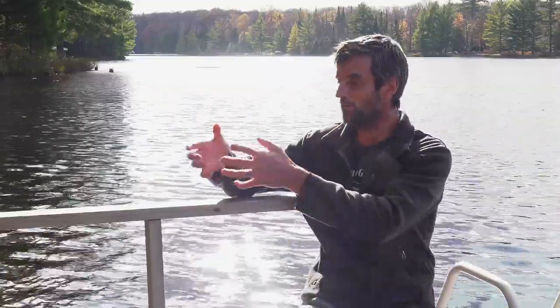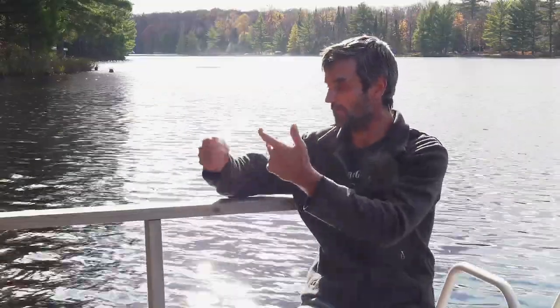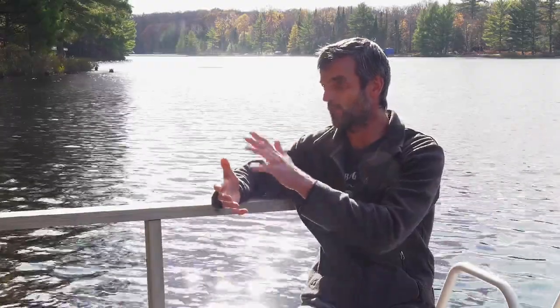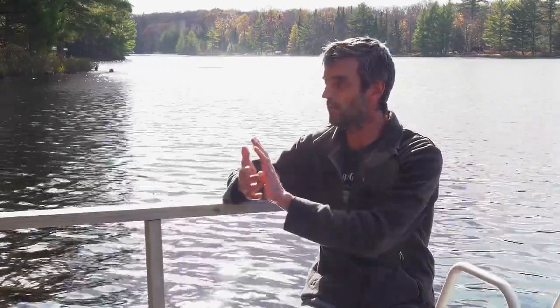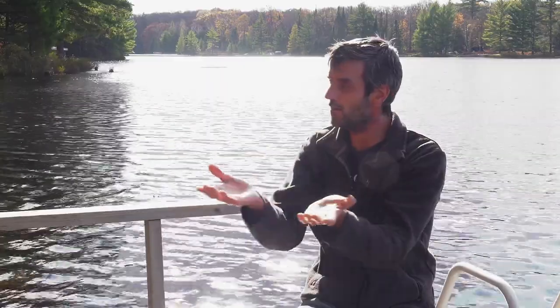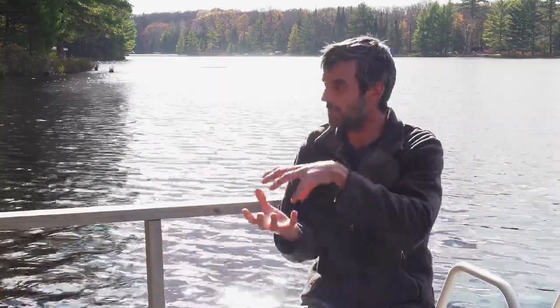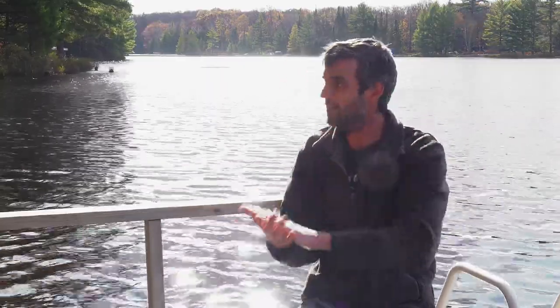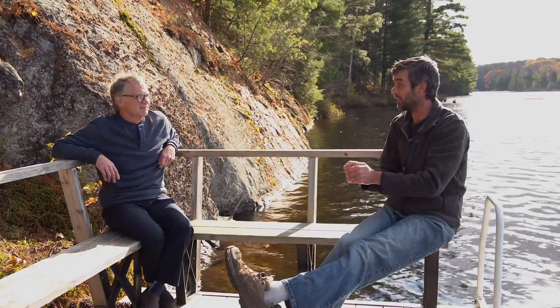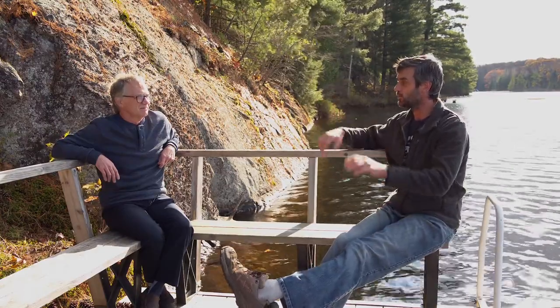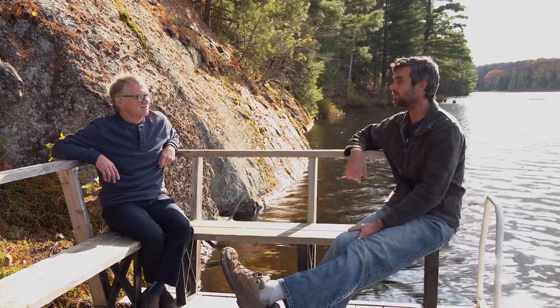Those hoods are made to pop off. Typically, the screen will fall out. And in 3 to 5 years, if you never clean that, like if you've ever seen your dryer exhaust hood, how it starts to plug up with lint, it'll be matted solid. And no air is getting in. Then again, everything sounds fine. You hear it working, but it's only half working and not doing what it was intended to do.